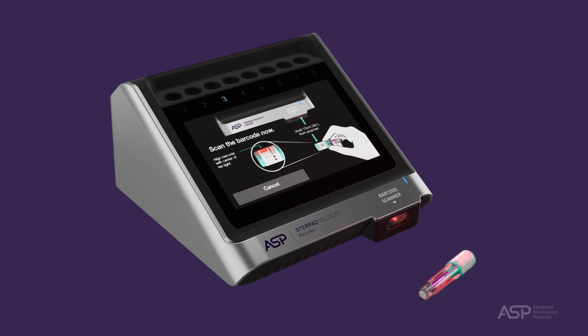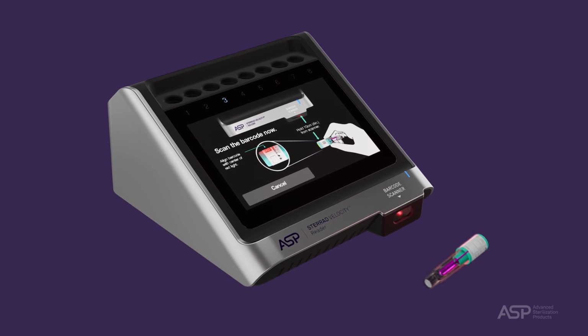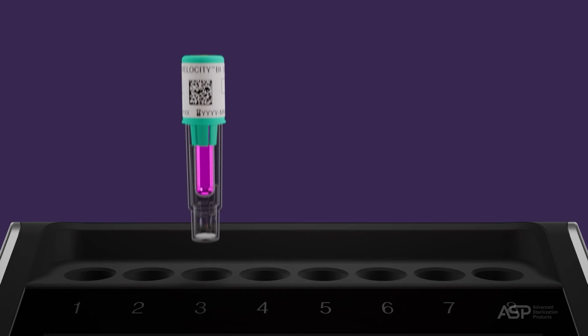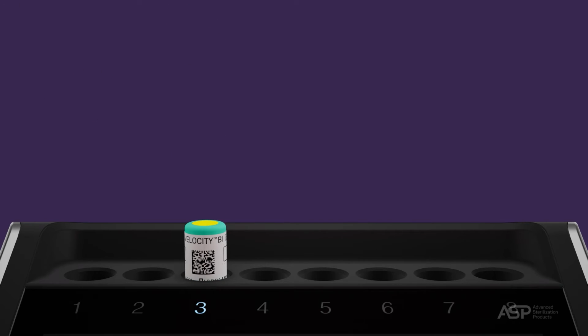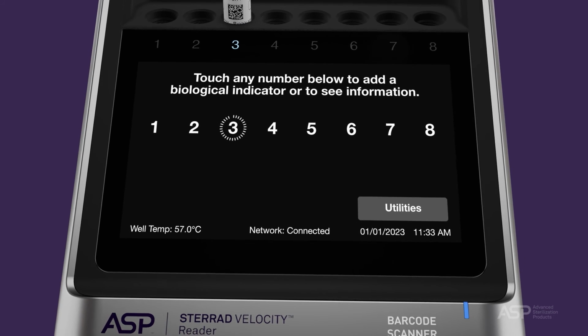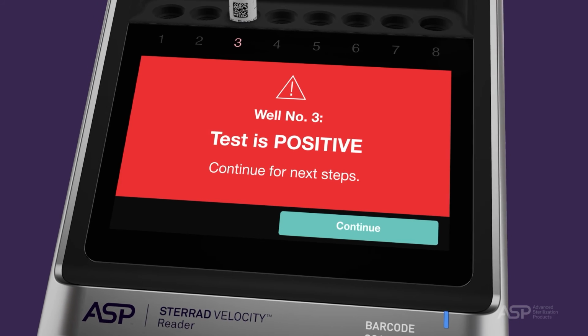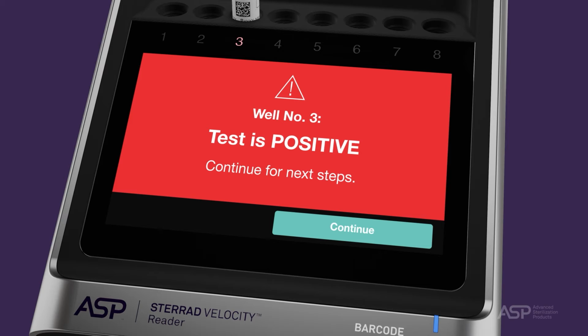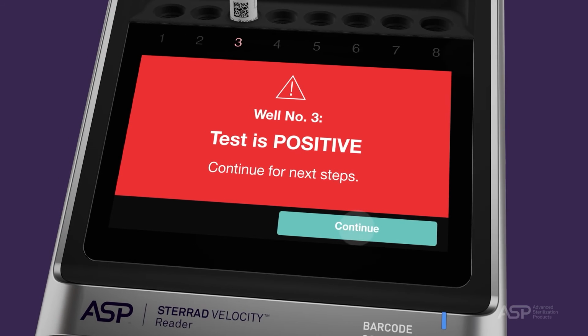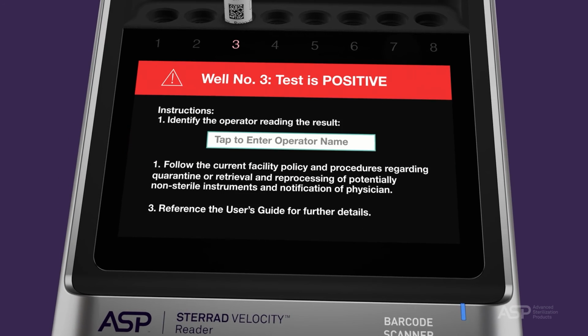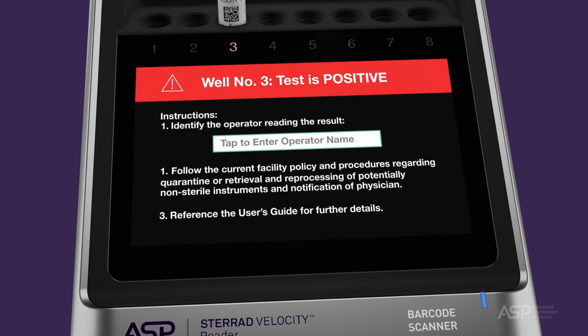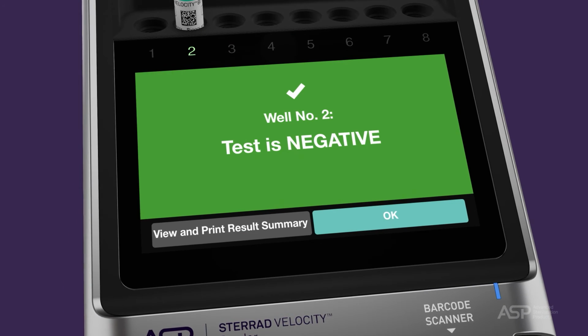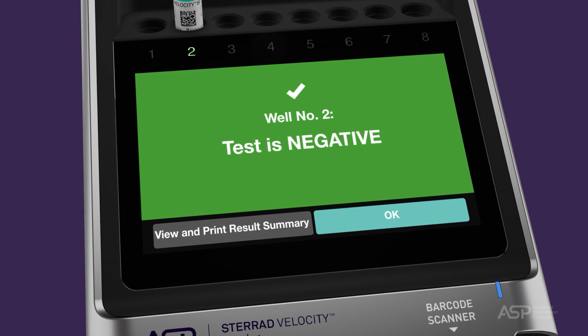The BI/PCD must be placed in the STERRAD Velocity Reader within the time frame specified in the instructions for use. The system will ask the user to contact an ASP representative if the reader detects 2 out of 3 test biological indicators are positive. You will continue to receive this warning after each sterilization cycle completion until 2 consecutive STERRAD Velocity Reader test BIs are negative.